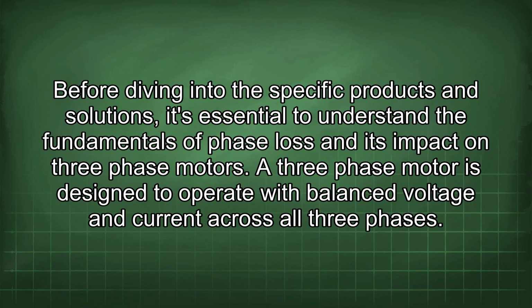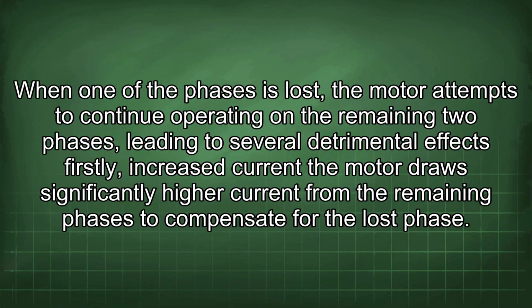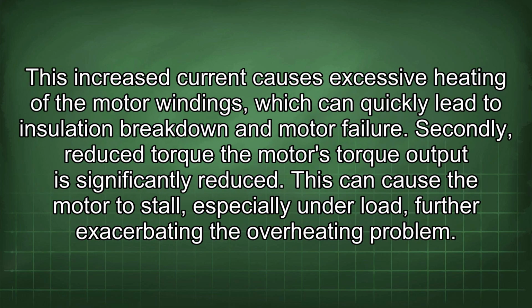Before diving into the specific products and solutions, it's essential to understand the fundamentals of phase loss and its impact on three-phase motors. A three-phase motor is designed to operate with balanced voltage and current across all three phases. When one of the phases is lost, the motor attempts to continue operating on the remaining two phases, leading to several detrimental effects. Firstly, increased current. The motor draws significantly higher current from the remaining phases to compensate for the lost phase. This increased current causes excessive heating of the motor windings, which can quickly lead to insulation breakdown and motor failure.